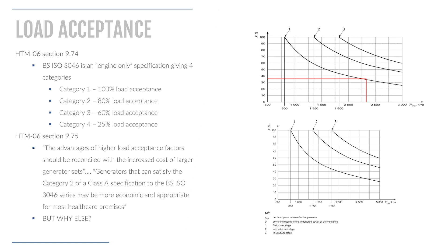To begin this quick review, we'll consider generating set first step load acceptance. This is an important consideration when it comes to selecting a new generating set. Here we see something of a mismatch between the ISO standard 8528 and the guidance given in HTM06. As we know, a generating set is a combination of an engine, alternator, control system, bed frame, etc. In ISO 8528, it is important to note that there are no specific requirements set out for first step load acceptance.